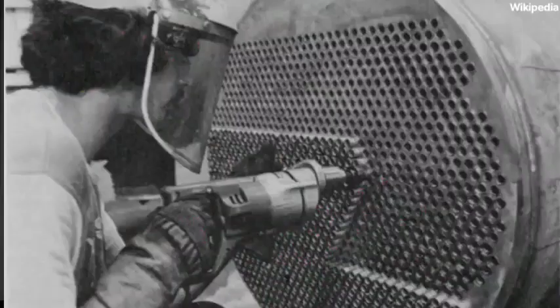So it will be 12 mm. Now you are drilling the tube sheet, so how much is required? 24. So 12 mm RF you are already getting, extra 12 mm you are drilling. So that means the calculated thickness consideration should be 88 mm. So you should put in PV Elite 88 mm, not 100 mm, but actually nobody puts it like that. So my query, which Atul raised, is did anybody ask why or how much thickness should be considered? He said no, if I consider 100 mm it's okay. Nobody asked that question. Yeah, if you consider 100 mm in the PV Elite calculation, that's okay.